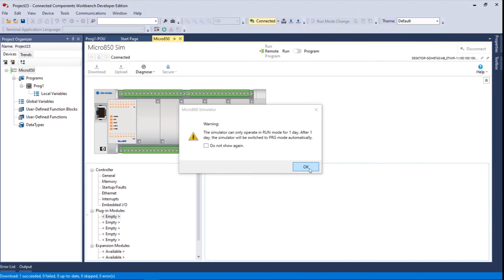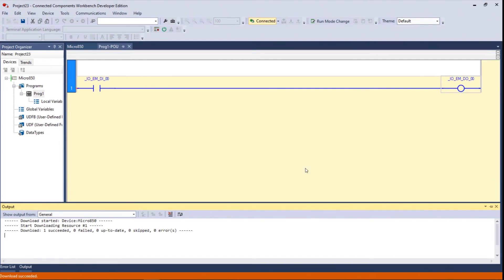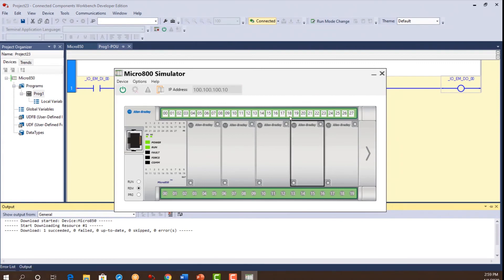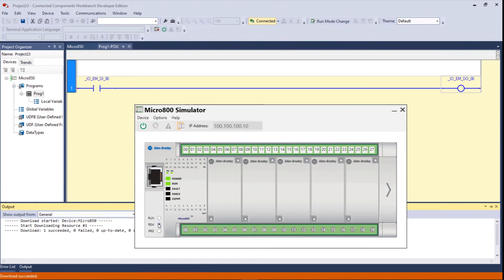Change the controller to remote run to execute the project — I say yes. I have the developer's edition so I can run for one day — 24 hours. Yours is only going to run for 10 minutes. Click OK to acknowledge. You can see the rung of logic: if input zero is on then turn on output zero — the DI digital input and DO digital output. Let's pop the simulator back up. We're in run mode now. I can toggle to program mode and back to run mode. You always want to leave it in remote, meaning you have remote access to it.